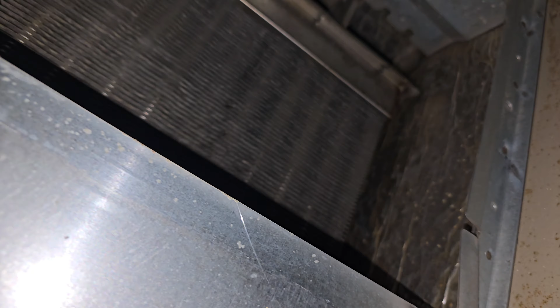You don't want to, after taking this blower wheel out, skip cleaning the secondary heat exchanger to make sure it's clean. Here's my secondary heat exchanger, you can see it's clean. I brushed it to make sure there's no dirt hanging in there, so now it's really clean, you can see it.